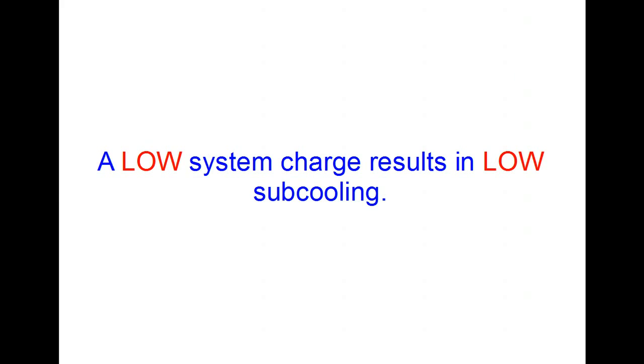So when you have a system that is metered using a TXV, a low system charge results in low or zero, no subcooling. And just remember that's because when you don't have as much refrigerant in the system as you should, you don't have that traffic jam, that backup of refrigerant into the condensing coil so that it can reach its proper subcooling level.